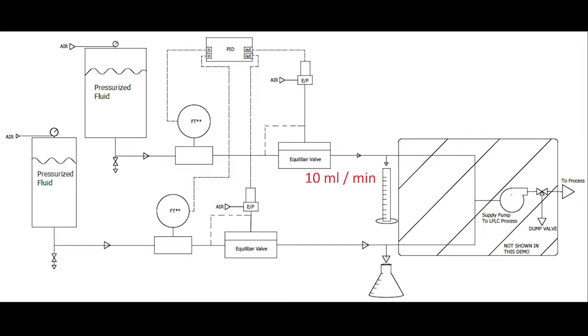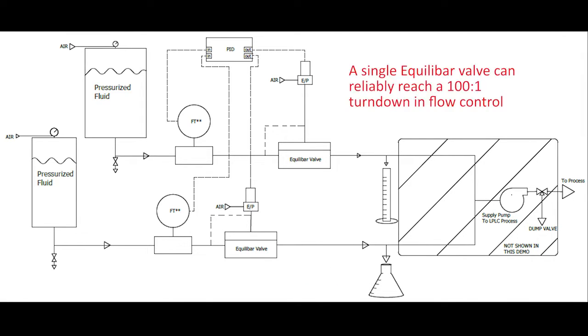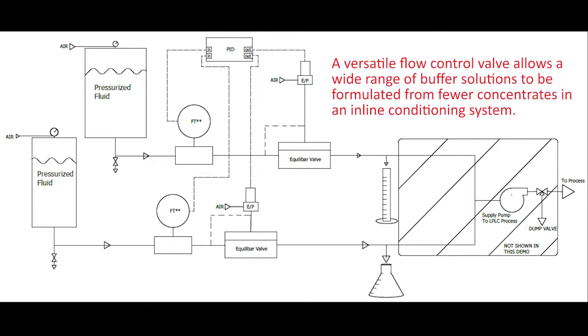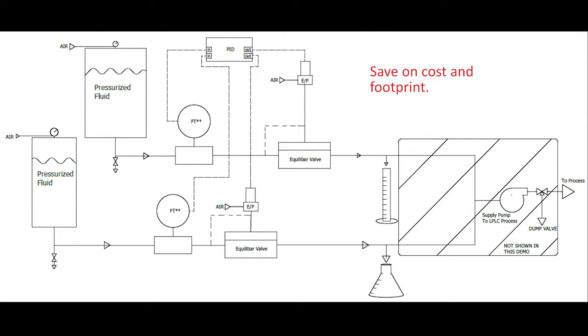The first FDO4 regulator is set to control at 10 milliliters per minute, while the second is set to control at 1,000 milliliters per minute. This really is intended to demonstrate that one single Equilibar valve can reliably reach a 100-to-1 turn down in flow control. The big benefit of this is it would allow a single buffer solution system to formulate a wide variety of solutions. Because you don't need a large volume of stock solution, you save on both cost and footprint.